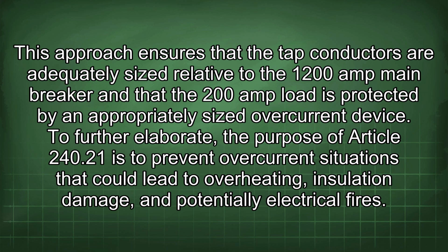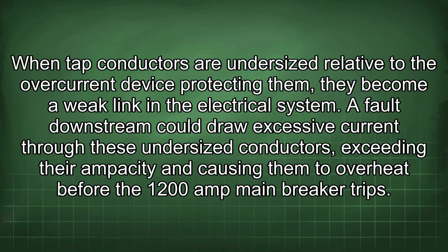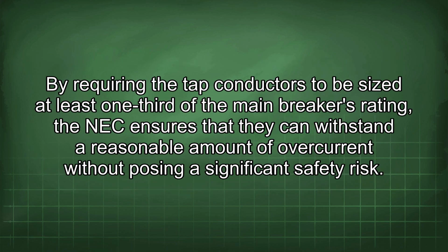To further elaborate, the purpose of Article 240.21 is to prevent overcurrent situations that could lead to overheating, insulation damage, and potentially electrical fires. When tap conductors are undersized relative to the overcurrent device protecting them, they become a weak link in the electrical system. A fault downstream could draw excessive current through these undersized conductors, exceeding their ampacity and causing them to overheat before the 1200 amp main breaker trips. By requiring the tap conductors to be sized at least 1/3 of the main breaker's rating, the NEC ensures that they can withstand a reasonable amount of overcurrent without posing a significant safety risk.